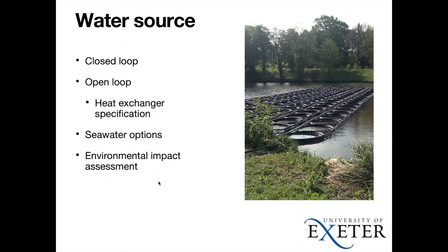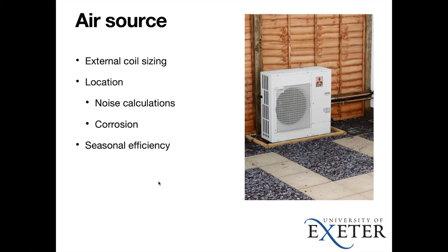Then if we include air source, because there are times when that's appropriate, we've seen examples where things like noise from the external fans has not been considered. We're relatively close to the sea, and we've seen projects with real corrosion issues, salty air coming through the fans causing poor corrosion. We help students properly understand the seasonal efficiency from an air source heat pump.